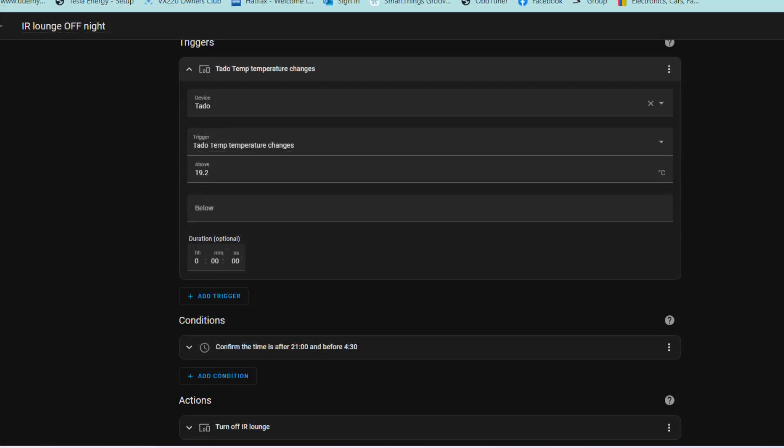And as for turning off the infrared heater at night, if it gets above 19.2 degrees between nine o'clock at night and 4:30 in the morning, it simply turns the heater off.